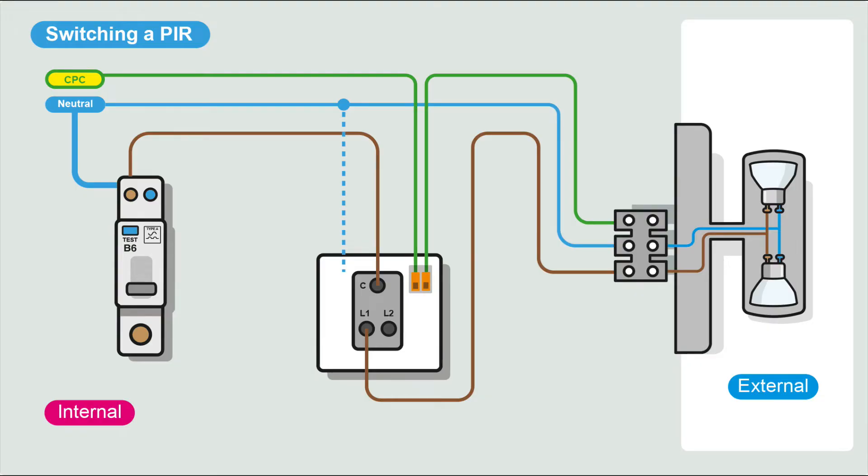So here's a circuit without the PIR added. This is just a switch. We have the power coming in - in this case it's from a B6 type A RCBO. Lighting circuits now require RCD protection. Live comes into common in the switch, leaves L1, and goes to the light. So that's an outside light - you have to physically switch it on or off.